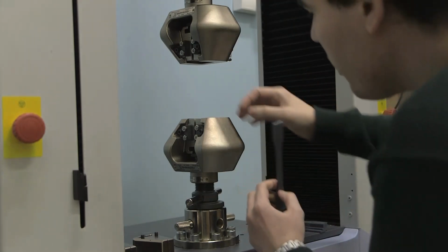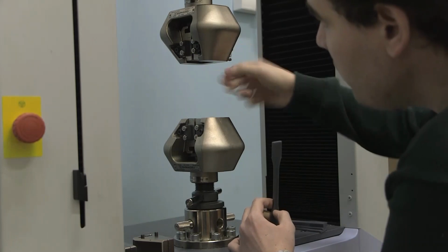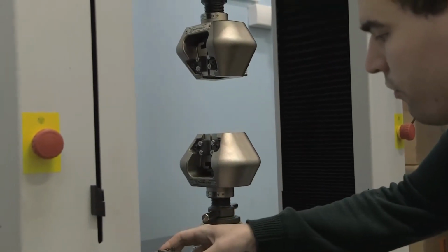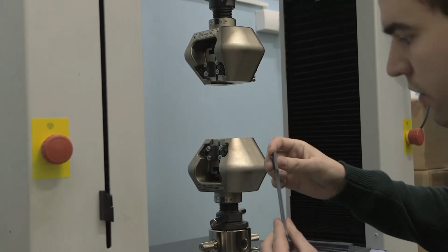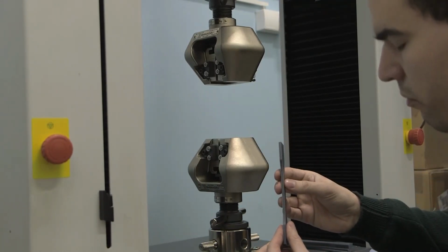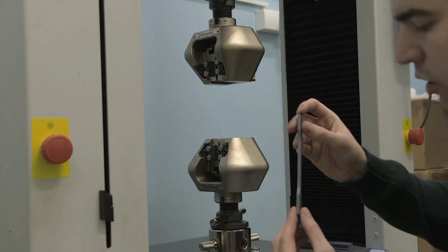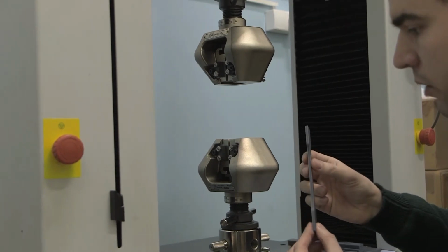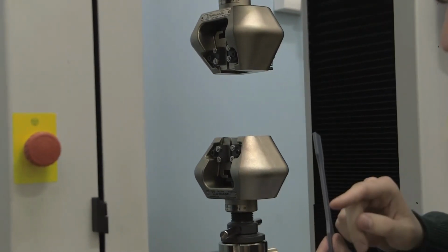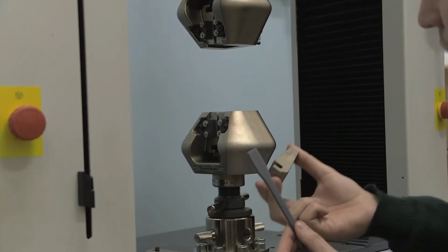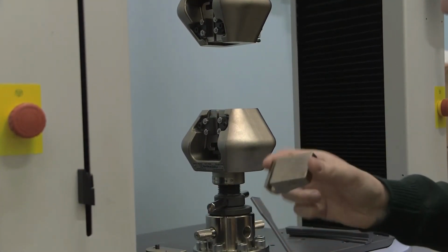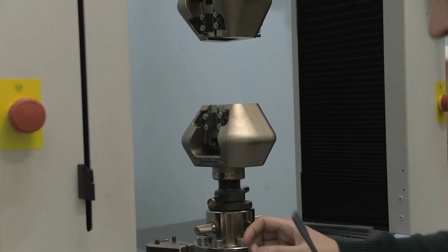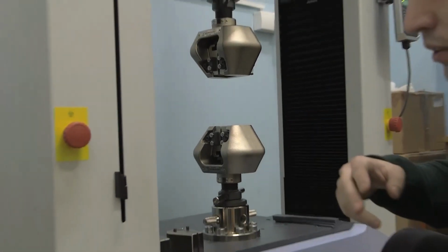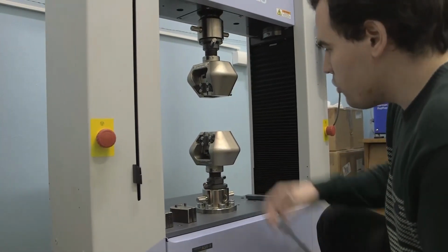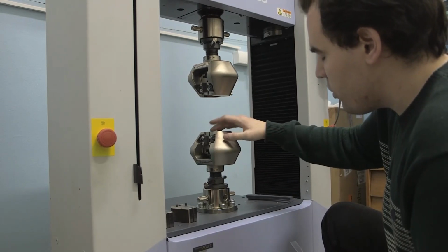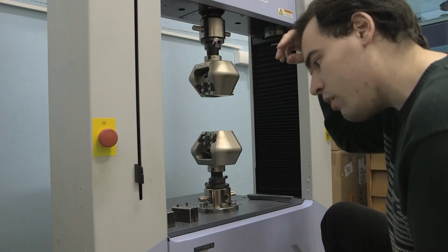So the plates are inserted into the jaws. There are different plates for different thicknesses of the specimen. They have an increment of about 7 millimeters. This specimen has a thickness of 4 millimeters, so we will use plates for 0 to 7 millimeters thickness of specimens. Here we have 7 to 14, and also we have plates for testing of materials that are from 14 to 21 millimeters. So the inserted plates are for thickness of 0 to 7 millimeters.